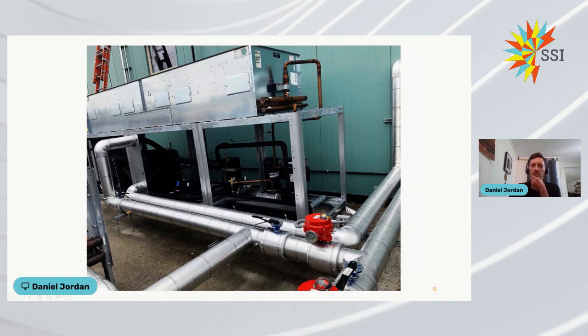But the big difference between a chiller and a dry cooler is that, as I mentioned earlier, a chiller uses the vapor compression refrigeration cycle, just like a refrigerator. So these 2 little black units, they look sort of like fire hydrants to me, are compressors, and they are responsible for manipulating the pressure and temperature of the refrigerant to dump heat. An easy way to identify whether you're looking at a chiller or a cooler is to look for the compressors. And similarly, if you see a lot of high surface area, small copper piping of different diameters, that's probably refrigerant running in there.